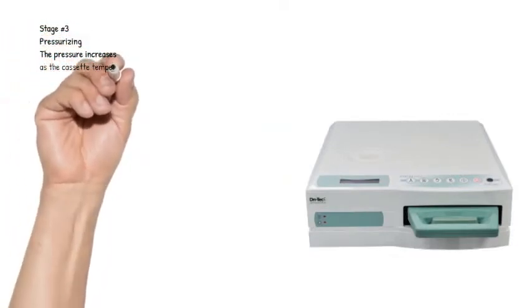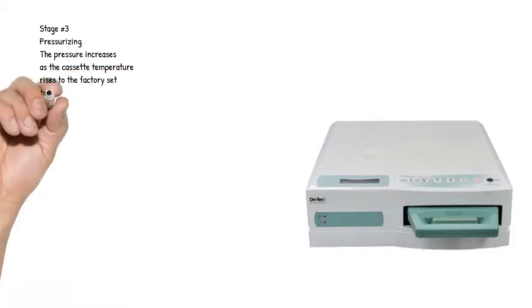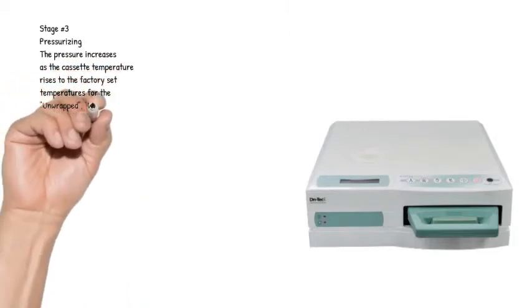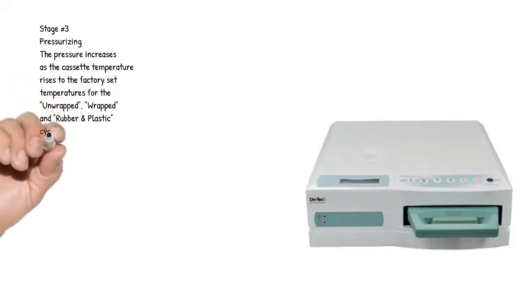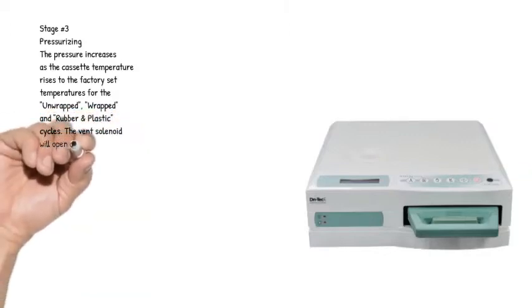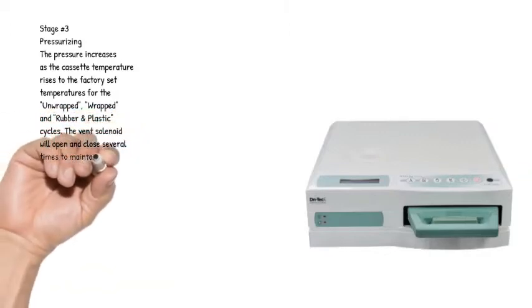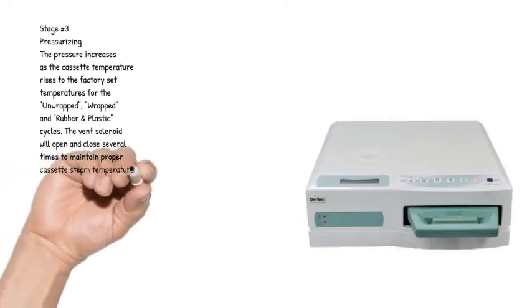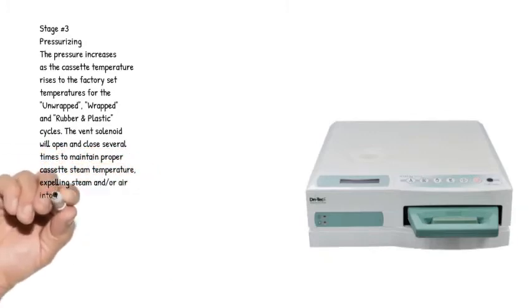Stage number 3. Pressurizing. The pressure increases as the cassette temperature rises to the factory set temperatures for the unwrapped, wrapped and rubber and plastic cycles. The vent solenoid will open and close several times to maintain proper cassette steam temperature, expelling steam and/or air into the condenser waste bottle.